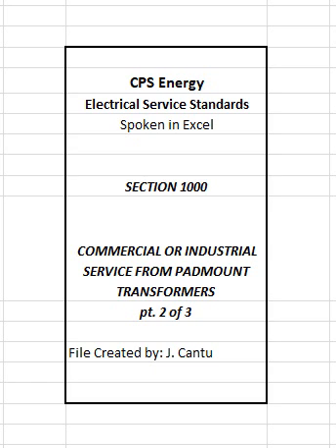9. Customer shall sufficiently size tap box to accommodate CPS Energy conductors and all customer conductors. 10. Customer shall designate a space in the tap box closest to wireway penetration for CPS Energy to terminate its cables to the bus bars. Customer cables and conduits shall not obstruct or interfere with this dedicated space. All connections must be accessible through cable tap box doors, refer to Figure 1001.